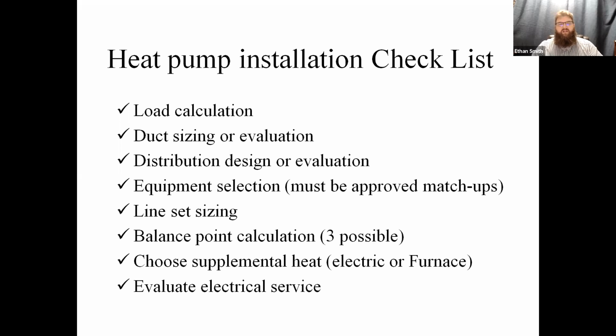The federal government has laws on the books now. There's talk of them starting to run random audits on contractors. Not sure how that's going to work out, but basically, if you can't produce an AHRI number for your installation, you're going to have problems. I will tell you, if you don't have approved matchups on heat pumps, you're going to have problems. I'll also warn you that going outside of the brand matchups, using a third-party evaporator or a third-party indoor coil on an OEM outdoor coil, sometimes can cause you problems.